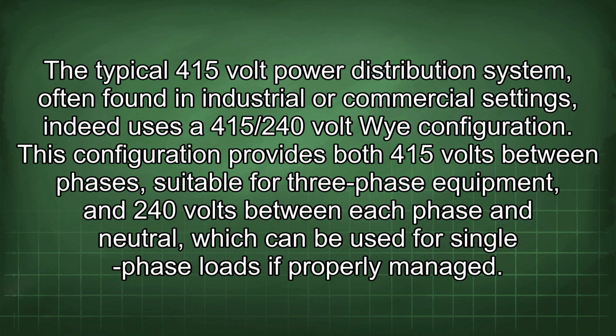The typical 415-volt power distribution system, often found in industrial or commercial settings, indeed uses a 415/240-volt Y configuration. This configuration provides both 415 volts between phases, suitable for 3-phase equipment, and 240 volts between each phase and neutral, which can be used for single-phase loads if properly managed.